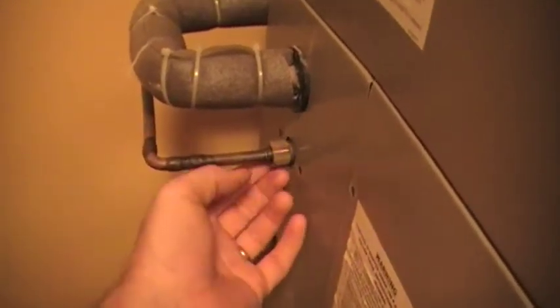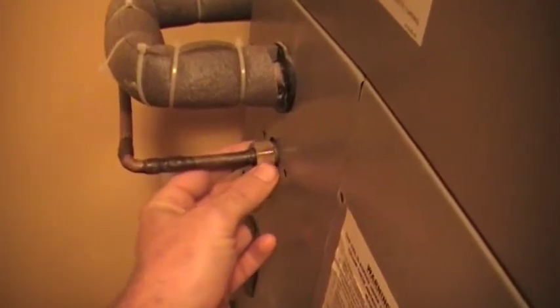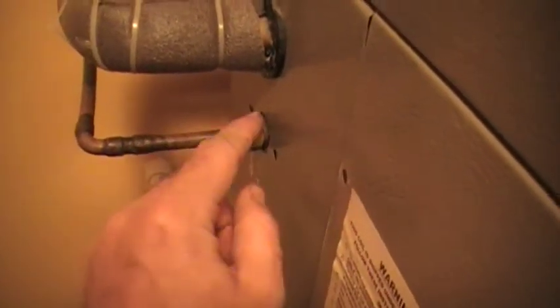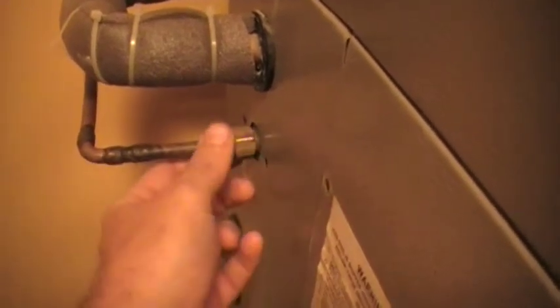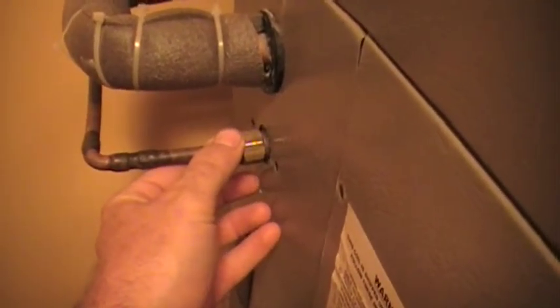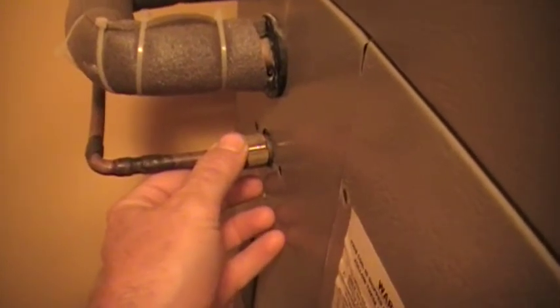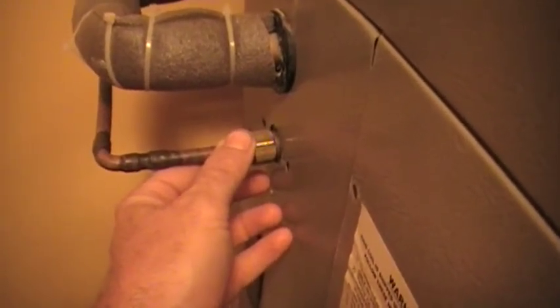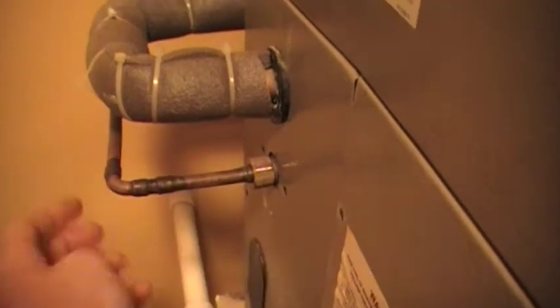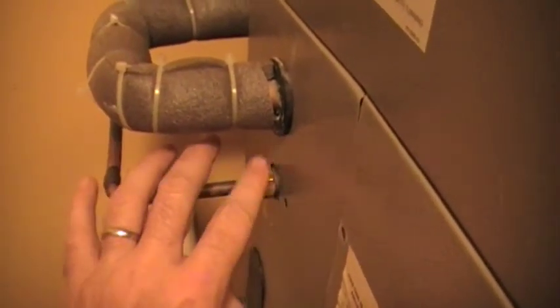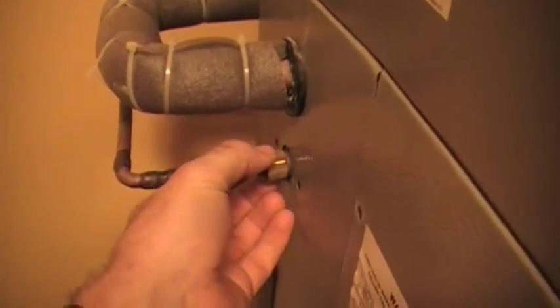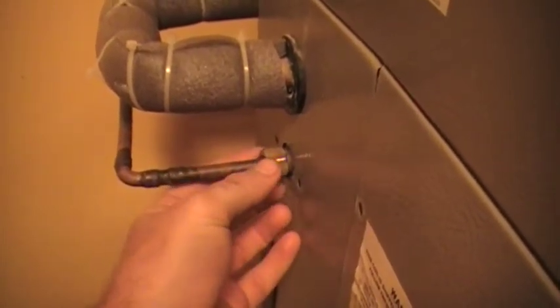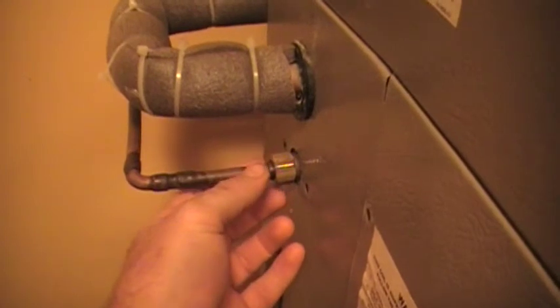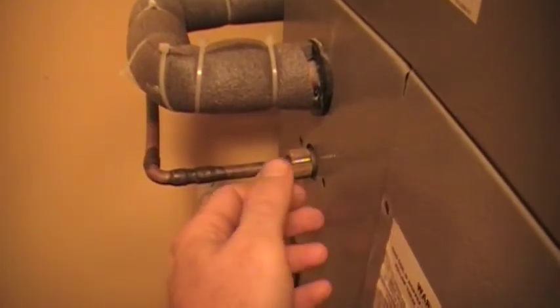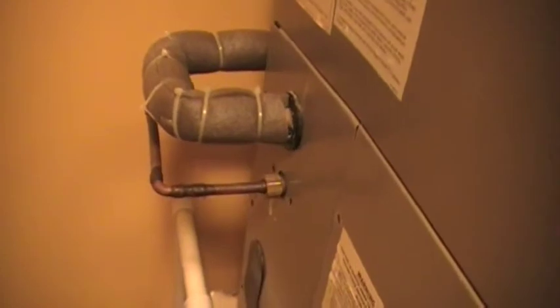And right behind this fitting right here is going to be a small orifice. If I'm not mistaken, I think I put an orifice inside this one that's equal to 55 thousandths of an inch. That's going to be my metering device right there. That's what's going to spray the high pressure liquid refrigerant into the larger pipe, which is going to be in the evaporator. And I'm going to turn this unit off.